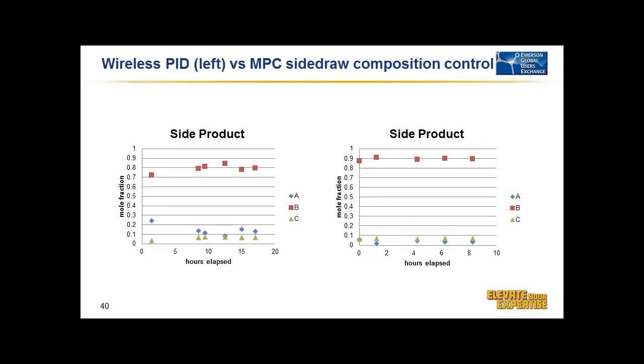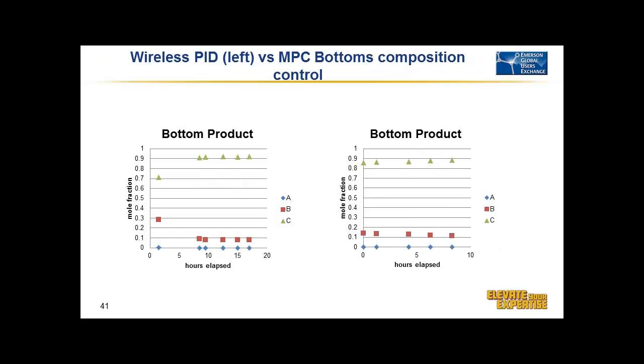Again, our side products, much steadier with MPC than with PID control. So this is how we like to operate going forward, this MPC steady state. And again, the bottoms product, very steady with MPC.